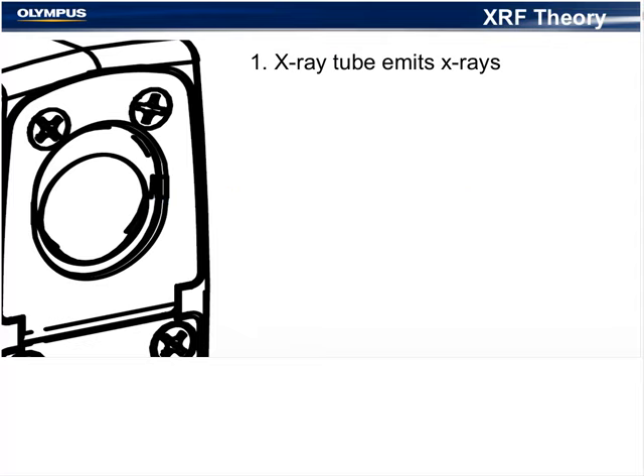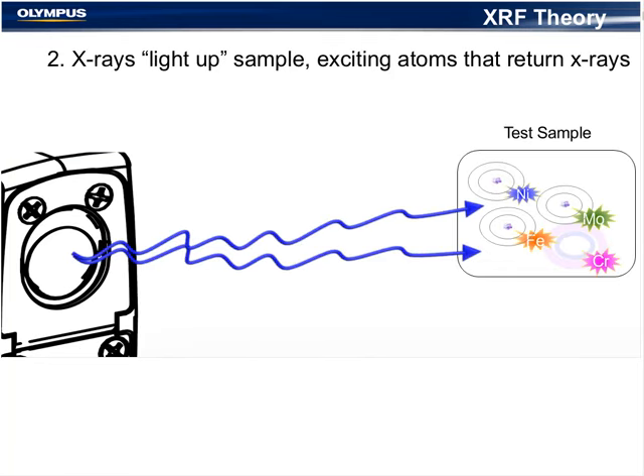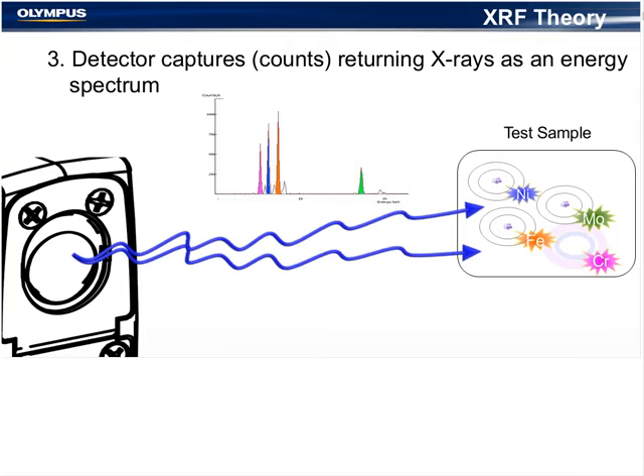So now I want to take a minute to talk about how XRF is able to provide these real-time quantitative values. Using an X-ray tube, we start by creating and directing an X-ray beam into the sample material. The lighting up of the sample occurs when the X-ray energy temporarily knocks an electron out of its orbital, ionizing an atom. In the process of transitioning from a positive ion back to electrically neutral, the lit up sample emits an X-ray energy that is specific for each element.